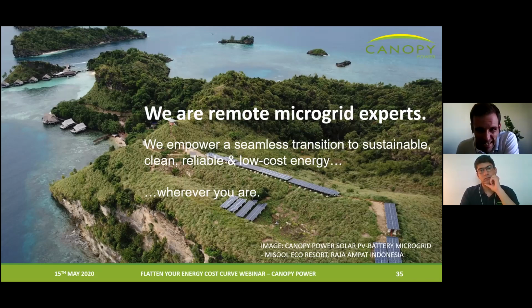So 20% is typical. Now this one: would a microgrid system with only PV and battery provide better savings in the long term, particularly for a new installation? Without a genset, it's not practical. You'd need a hugely oversized PV and hugely oversized battery to cater for periods like the monsoon season where you don't get any real sunlight for 3 or 4 days in a row. You'd have to have such a big system and it would cost so much that it wouldn't be practical. So it's always best to have a genset there for that last bit. We can practically get to 85-90% without going too crazy on the price, but going beyond 90% is just not practical at this stage.